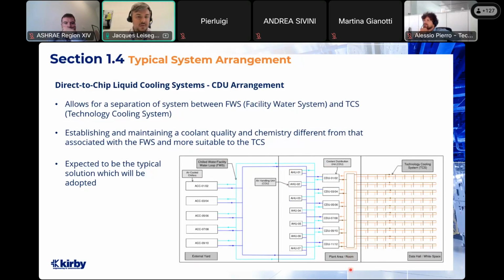You could, theoretically, cool your servers directly with the chilled water system and have it as one common loop. The risk here is that you have a much larger system volume, which you're exposing your white space to in case of a leak. And you're increasing the volume of coolant that you may need.